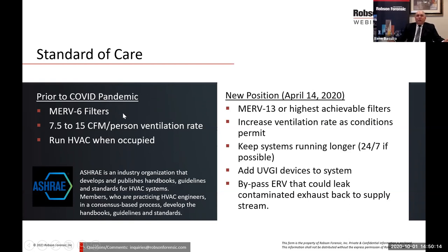Prior to the COVID pandemic, the filter recommendation was MERV 6 filters. Remember MERV 6? Very close to MERV 4, which really didn't filter out much other than dust and pollen, and maybe just a little bit more efficient than the MERV 4. ASHRAE recommends between 7.5 to 15 CFM per person ventilation rate in buildings, and they would recommend running the HVAC system when the building is occupied, right?